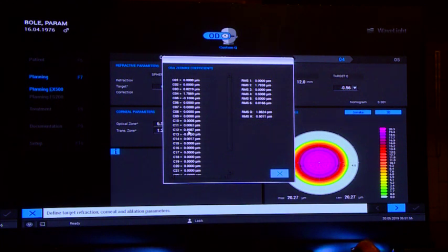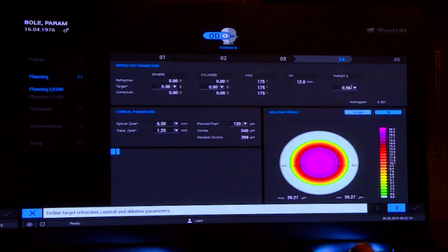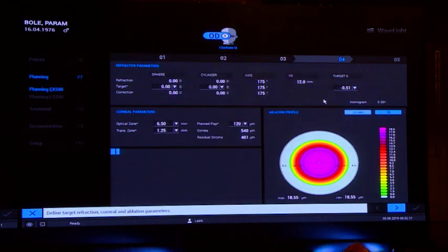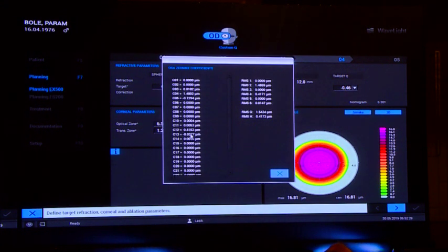So I do now an induction of plus 0.49 microns of spherical aberration. Now, if I want to achieve exactly 0.4, I know this is too much, okay? So this is the reason I took 56, just to show you what we could do. Let's do a 51, okay? Zernike's, 0.45, still a little bit too much. I don't remember what it was. I think it was 46. Let me see. So C12 is 0.41. Okay? This is what I want to induce, right?